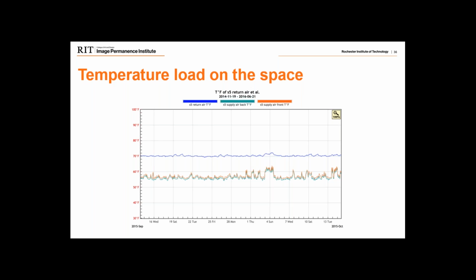So we go, what is causing that much of a heat gain? It's a significant heat gain. And when you walk through that collection space, you don't feel that. You don't feel any major humidity, any major gain. So this is something that would not have been known was occurring until we really started to delve deeper into that. And what was happening is the room had what was called an open plenum. So the air from the room was returned up into an open ceiling with no vents or ducts, and then pulled out of an actual vent back to the mechanical system on the wall. That was where our logger was, at that vent. So somewhere from leaving the room and then getting to the return vent in the wall up in the ceiling, we were gaining that 15 degrees.